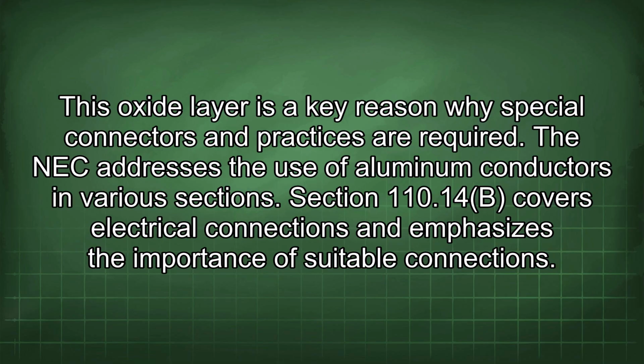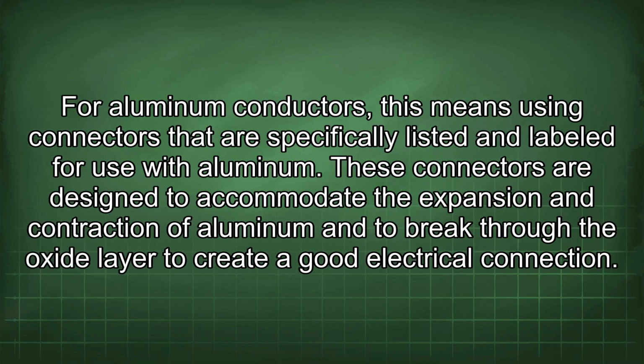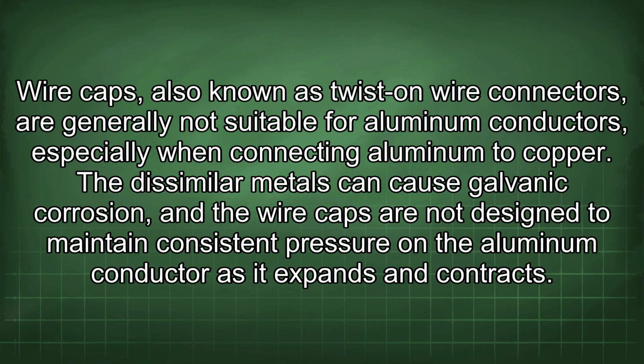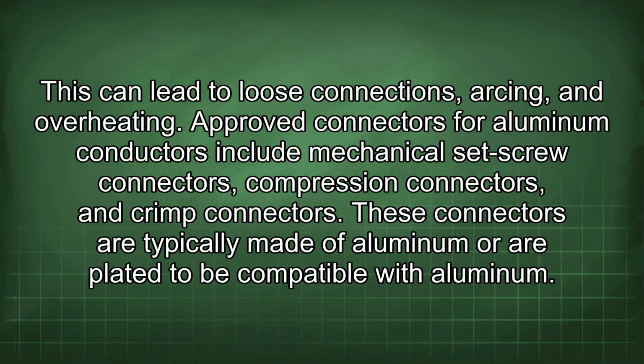The NEC addresses the use of aluminum conductors in various sections. Section 110.14(B) covers electrical connections and emphasizes the importance of suitable connections. For aluminum conductors, this means using connectors that are specifically listed and labeled for use with aluminum. These connectors are designed to accommodate the expansion and contraction of aluminum and to break through the oxide layer to create a good electrical connection. Wire caps, also known as twist-on wire connectors, are generally not suitable for aluminum conductors, especially when connecting aluminum to copper. The dissimilar metals can cause galvanic corrosion, and the wire caps are not designed to maintain consistent pressure on the aluminum conductor as it expands and contracts. This can lead to loose connections, arcing, and overheating.